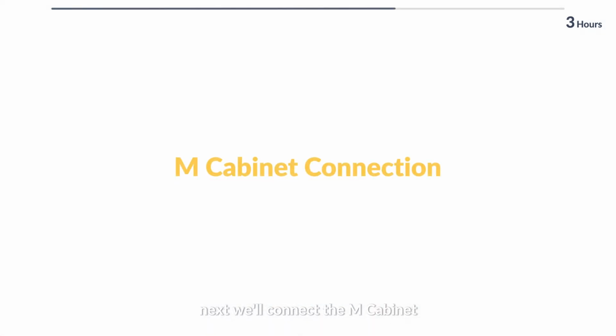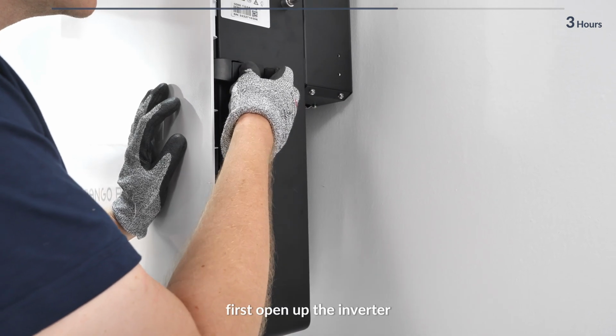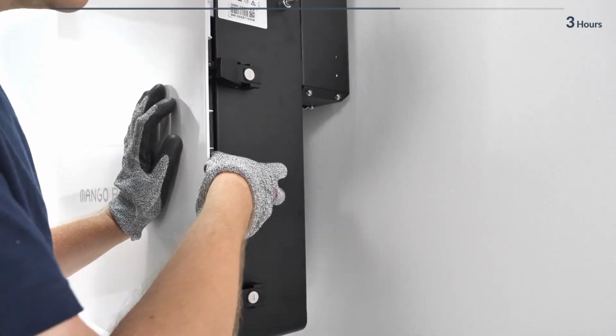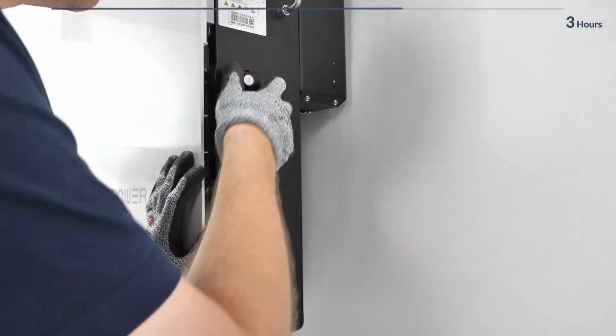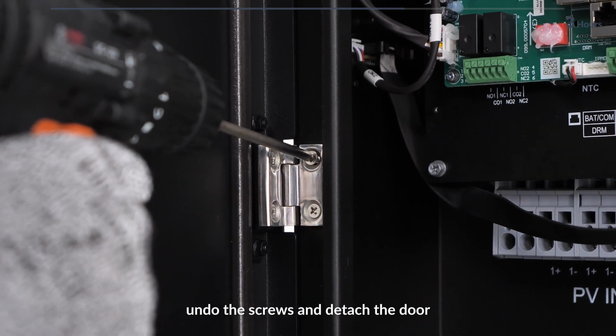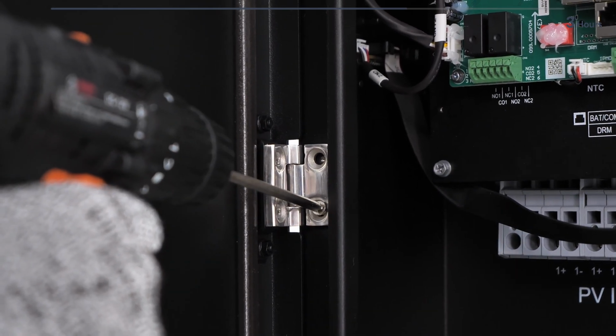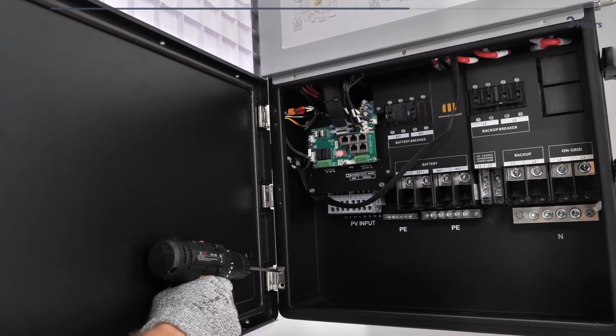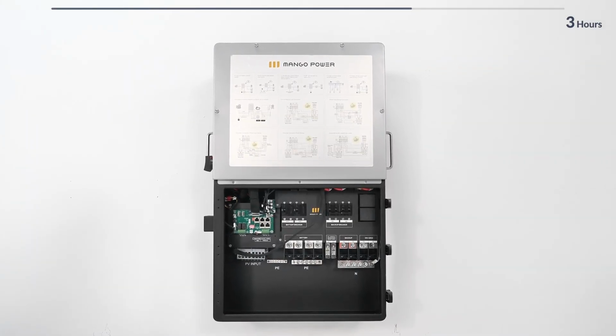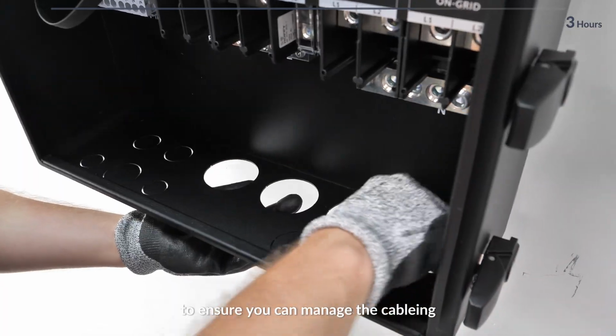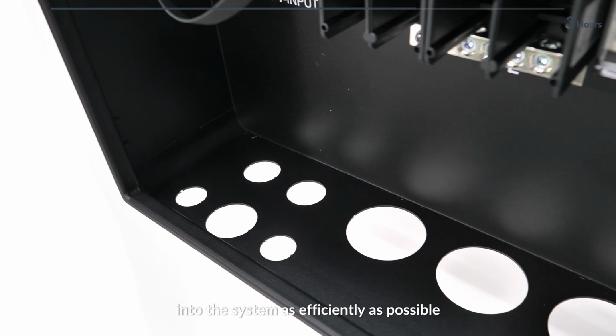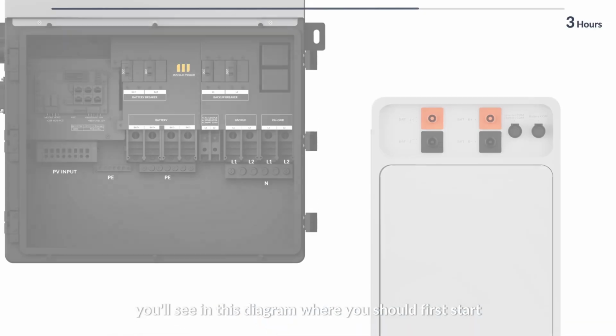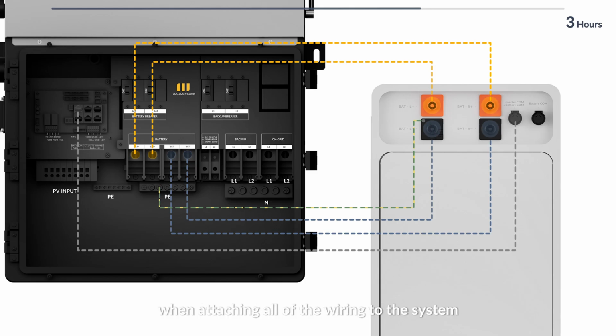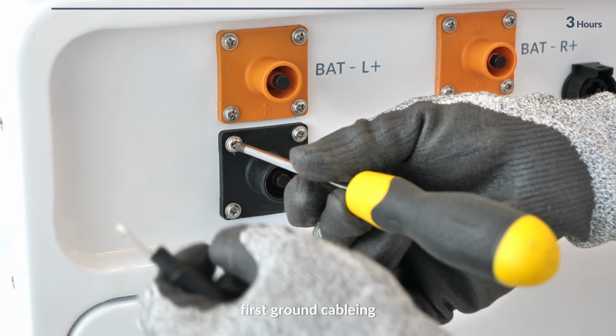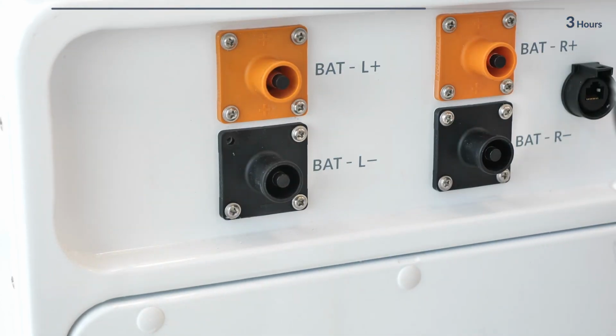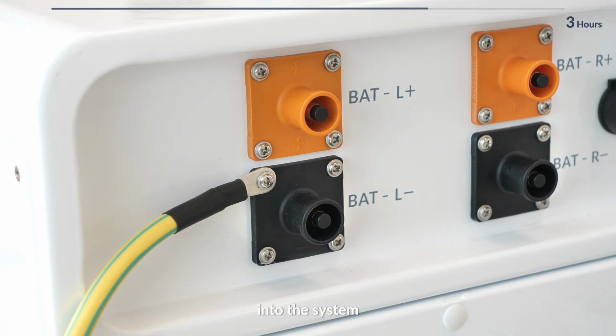Next, we'll connect the M cabinet into the hybrid inverter. First, open up the inverter. Undo the screws and detach the door. Knock out the holes to ensure you can manage the cabling into the system as efficiently as possible. You'll see in this diagram where you should first start when attaching all of the wiring to the system. First, ground cabling, attaching that through the bottom into the system.